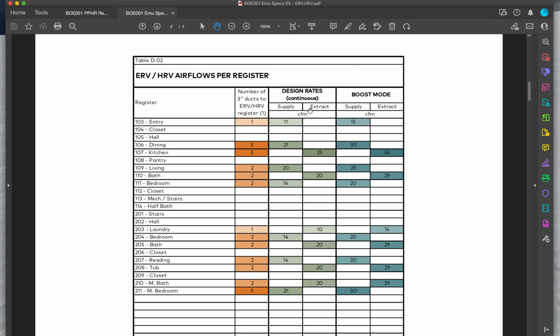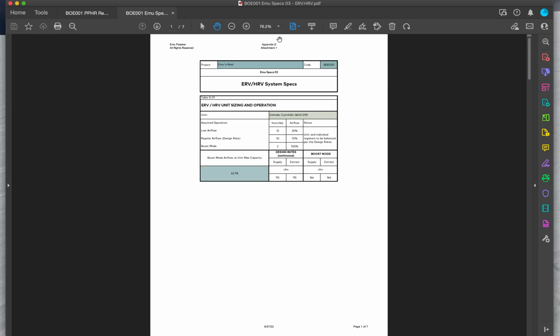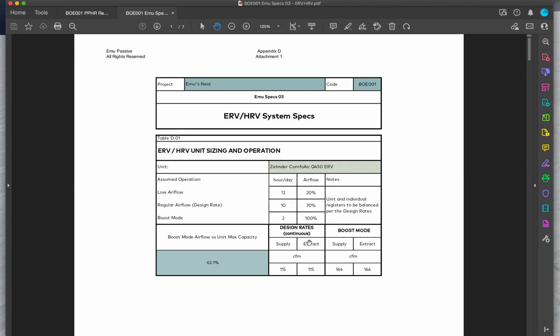If you supply more than you extract, you push warm, humid air into your assembly, causing moisture damage. If you depressurize the building, so if you're extracting more than you supply, you are pulling in pollution from the outside as well as particles from inside your walls. That may be particles of insulation, dust from construction, pretty nasty stuff. So we always spec the same supply as the extraction. In fact, looking back at the previous page, the two totals, total design rate, supply 115, extract 115, are the same because it's balanced ventilation.